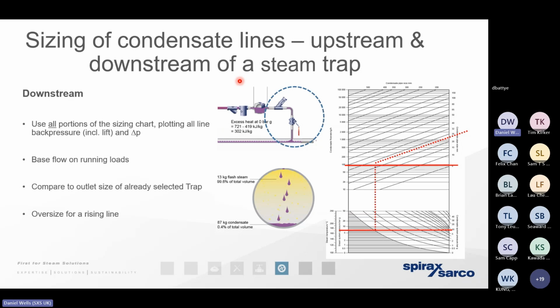So it's critically important that we think of condensate as a biphase. Condensate is only ever a single phase fluid at a stable pressure. So the table over here at the right-hand side of the screen is really demonstrating visually how we need to size condensate pipework whenever it's downstream of a point of depressurization. First of all, we take into account the mass flow rate, and then we take into account the depressurization. So the dotted line shows you how we correctly size a condensate pipework.